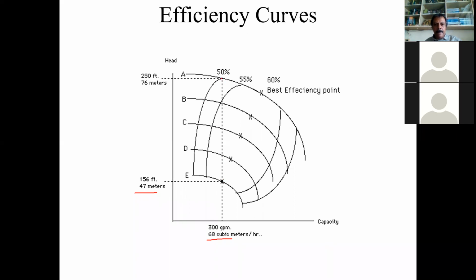If we choose A, then at this point, the head is here. At this point, you get the required flow rate, 68 meters cube. But the system head is only 47 meters. So for 47 meters of system head and your requirement of 68 meter cube, you have to throttle this pump, keep on throttling, increase the head. So it reaches 76 meters, then you get 68 meter cube per hour. Efficiency is going to be 50%.